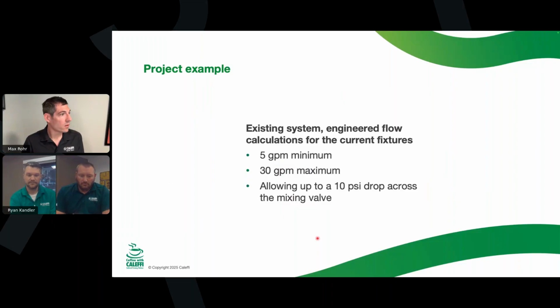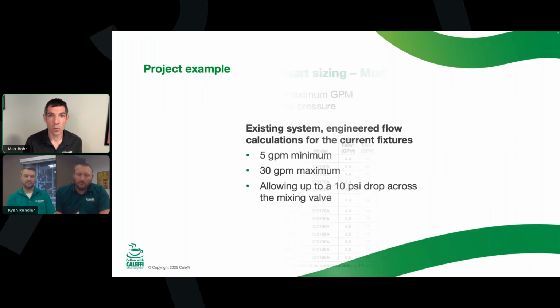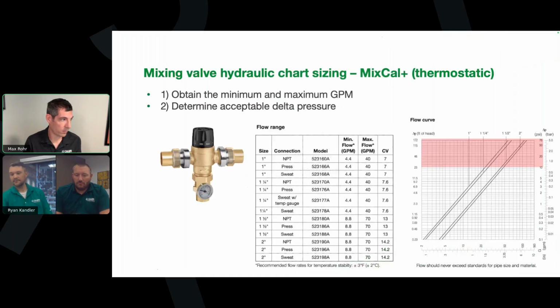Okay. Let's go through a project example to just see with one set of measurements here. We'll say that we have engineered calculations of a building that's going to need a 5 GPM minimum, 30 GPM maximum, and we want to set a pressure drop limit across the mixing valve of 10 PSI. Where does that line up here? So I'm going to go through these kind of quick and show you where they would line up with the two different products that we have. It's going to be similar with different mixing valves in the industry from other manufacturers too. This is just kind of a technology versus technology explanation here.